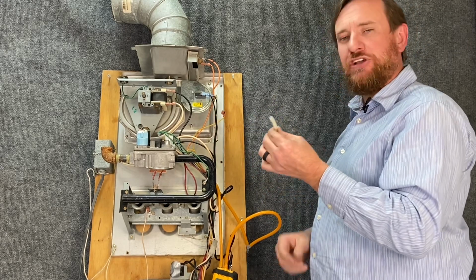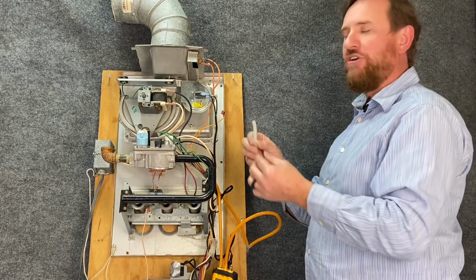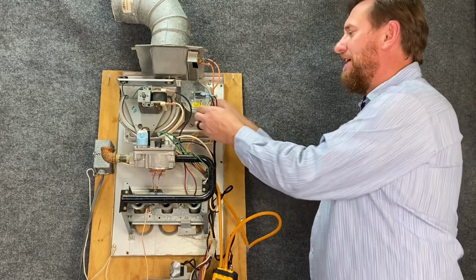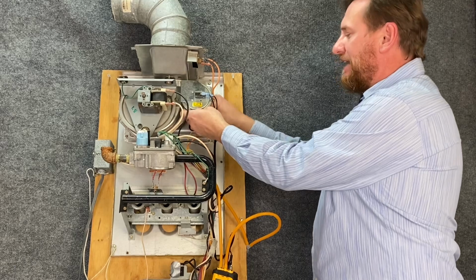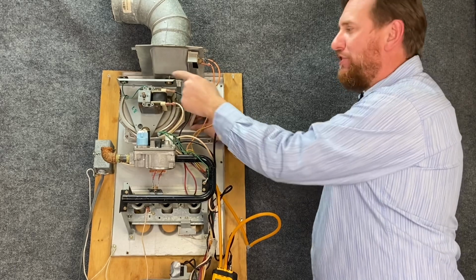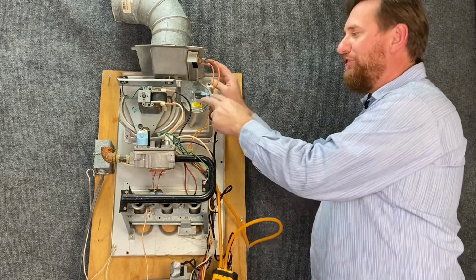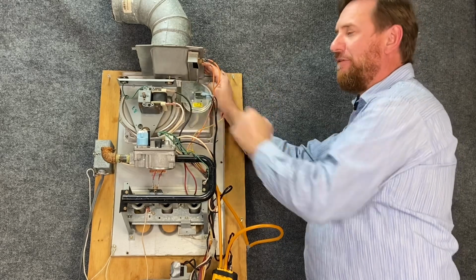I used to keep extra hoses with me just in case they cracked or broke. I can replace them and not have to worry about it. So just to recap, it's a safety device that makes sure this fan motor is working. Most of them are normally open. They close when we have the proper vacuum.